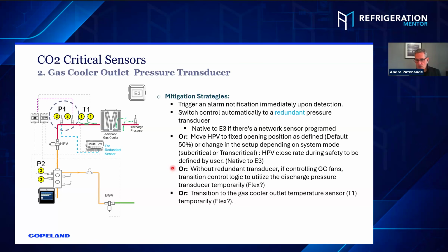Or another mitigation, without the redundant transducer, if controlling gas cooler fans, you can transition control logic to utilize the discharge pressure transducer, because you've got another pressure transducer there. Yes, the pressure will be slightly higher on the discharge side than the gas cooler side, but it gives you a pressure source that allows you to limp along until someone comes in and fixes the P1 sensor. Yeah, but the big thing is it involves a flex combiner to do that. But it's there. So basically you get an alarm. That alarm will trigger the flex combiner, and the flex combiner says, okay, we're not going to use P1 anymore. We're going to use discharge pressure, whatever that one is.